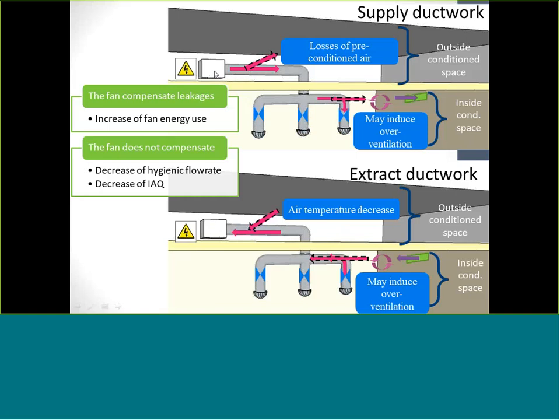Either the fan will compensate leakages. That means that the fan will run faster and faster to maintain the hygienic flow rate at the air terminal devices, but this means that leakages will increase the fan energy use. Or the fan will not compensate. That means that it will run at the same speed, whether there is a leakage or not, which means that you will have a decrease of the hygienic flow rate because part of the flow rate is going through leakage instead of going through air terminal devices, and then you may have a decrease of the indoor air quality of the building. So this is the theory.